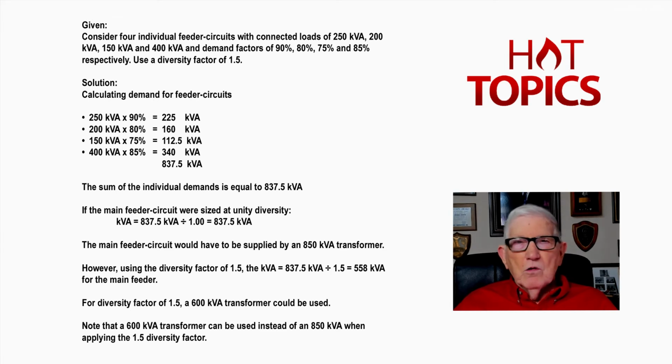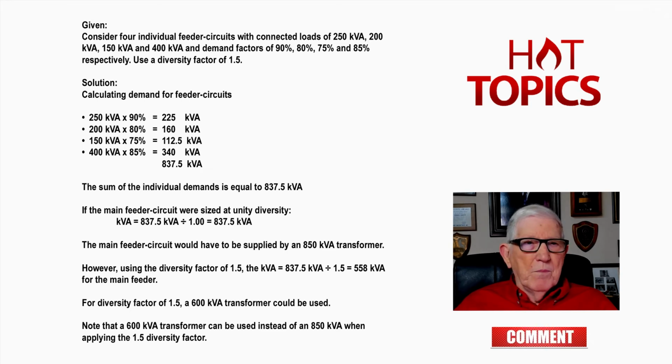Are the loads total electric in the facility? Are the larger loads gas and everything else electrical? Those kind of loads that are presented are available in not a dwelling unit in this case, but a commercial or industrial site. Then that would determine what kind of diversity factor that you would use. You'd use a diversity factor here of 1.5.